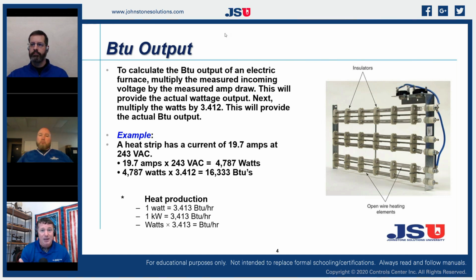So it's fairly common to pull a heat kit out and find deterioration on the elements and to find ceramic insulators that have gotten so hot that they have broken in half. And that's what we're there to do. We're there to evaluate this system. And the best way to do that is to understand what the elements are actually doing. How much heat are they producing and how much air are we moving across those things to make sure we are getting sufficient air. So we can calculate that fairly easily, actually.